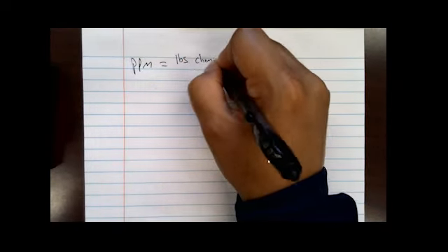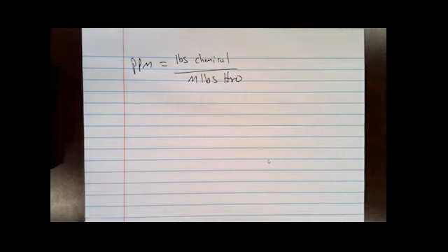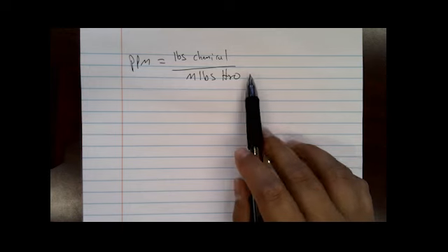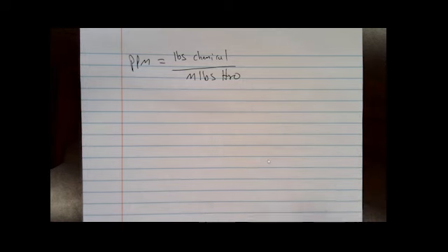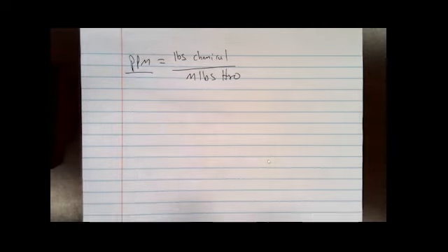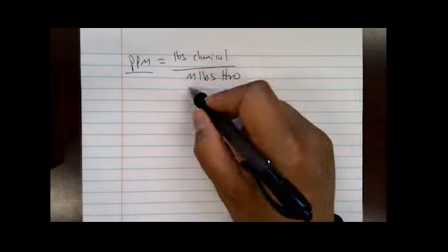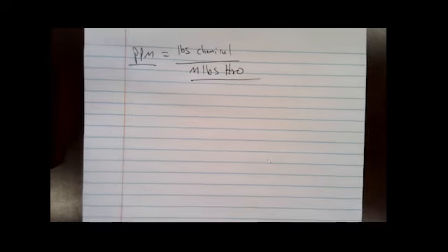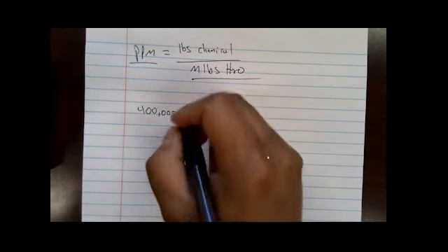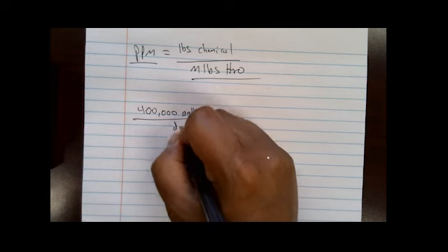So part per million is equal to pounds of chemical per million pounds of water, right? We're given the water treated per day, and we're also given the coagulation dose, 2 milligrams per liter. So in this case, we're given the ppm, and we're also given the million pounds of water. So let's first take a look at the water. We have 400,000, and that's gallons per day, right?